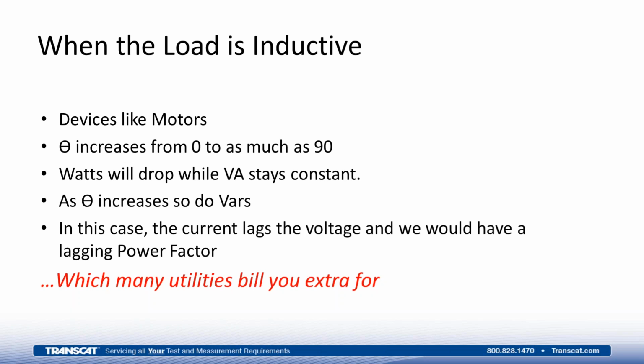When you apply things like motors to your electrical system, the motor does not draw current at the same exact instant as the voltage changes. And in fact, there is a phase angle between the motor's voltage and the motor current, meaning that theta increases from 0, that of a resistive load. It could, but it never does, increase to as much as a value of 90. And as theta goes up, what we find out is the VA will drop. I'm sorry, the watts will drop while the VA remains constant.